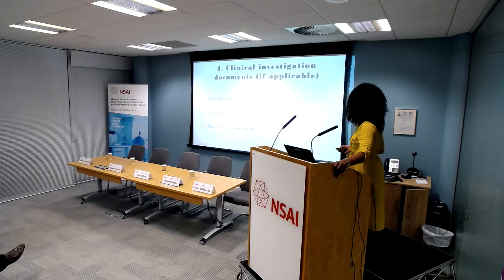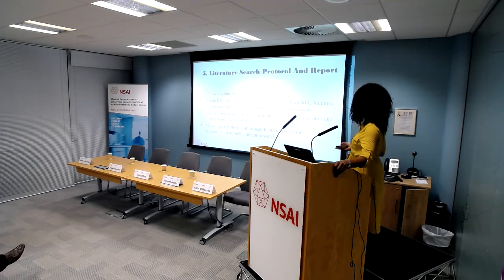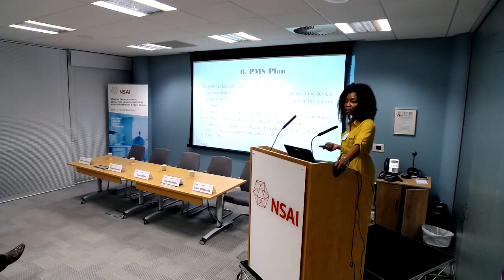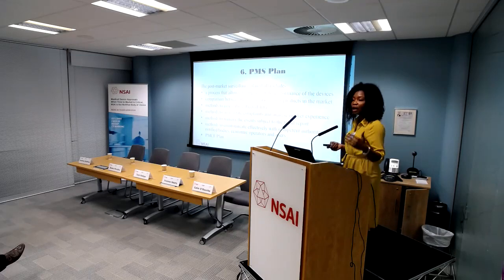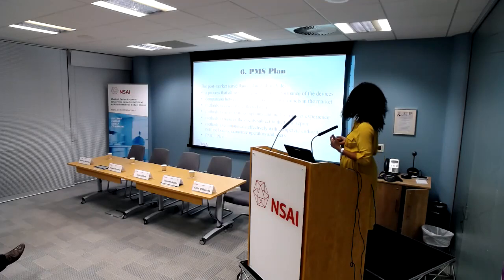If you're performing a clinical investigation, you'd also need a CIP, an investigator's brochure, and a clinical investigation report. And as I keep saying, you have to perform a literature search and provide a protocol and a report regarding your device. You need a PMS plan as well, that's a post-market surveillance plan. We need to see how you intend to follow your device when it's on the market. And in your post-market surveillance plan, we need to see your PMCF plan, which is your post-market clinical follow-up.